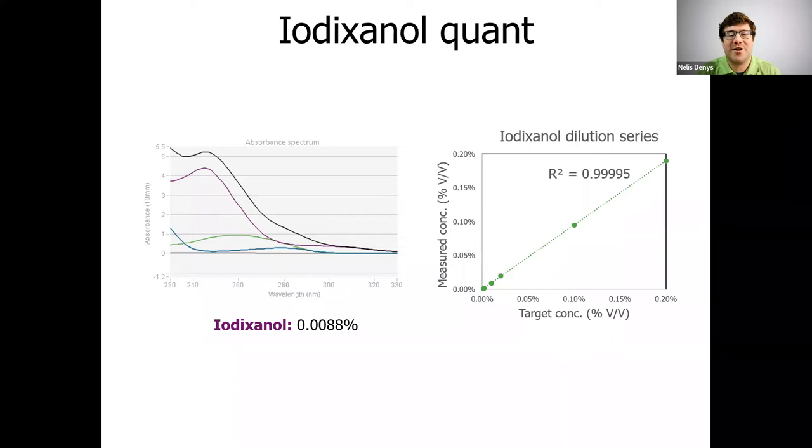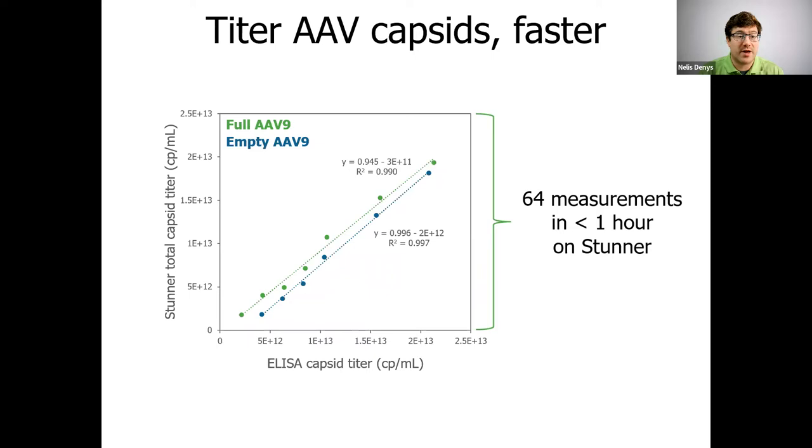Comparing to other techniques, for example, for getting capsid titer, Stunner is way faster and requires less upfront work than ELISAs. Here we've taken empty AAV9 and full AAV9 and ran dilution series on both, and we're comparing Stunner's total capsid titer versus the results of a capsid ELISA. You can see the results have slopes close to one and R-squared values above 0.99. But more importantly, it would take hours to get this ELISA data, while Stunner has done it in less than an hour with no sample prep at all.